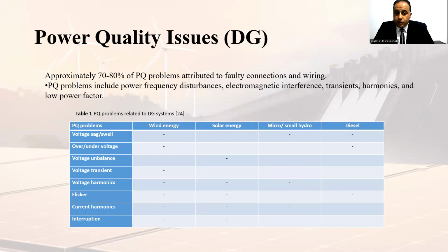On power quality issues, approximately 70 to 80% of power quality problems are attributed to faulty connections and wiring. Power quality problems include power frequency disturbance, electromagnetic interference, transients, harmonics, and low power factor. As shown in table number 1, the main power quality problems are voltage sag and swell, over and under voltage, voltage imbalance, voltage transient, voltage harmonic, flicker, current harmonic, and interruptions.